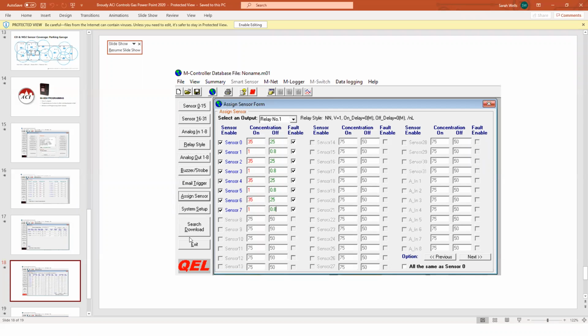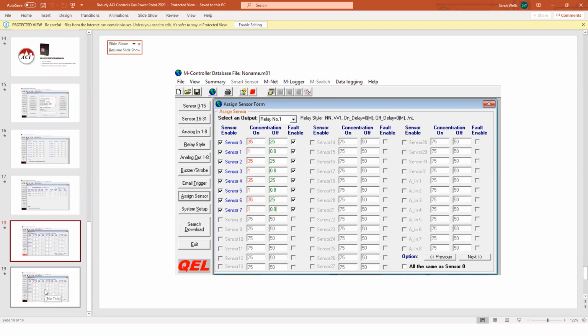And you can do that with relay number 2 also. Let's say this will be your first trip point. You can set relay 2 up for a second alarm level, let's say 50 parts per million for CO and 3 parts per million for NO2. You can then have relay 2 do whatever you want, turn on a horn and strobe, turn on a second fan. And then the third relay could be the same trip levels that would close a relay for a remote alarm someplace else to let somebody know that something's going on in the parking garage. So all these relays are programmable to whatever trip levels and alarm levels you want.